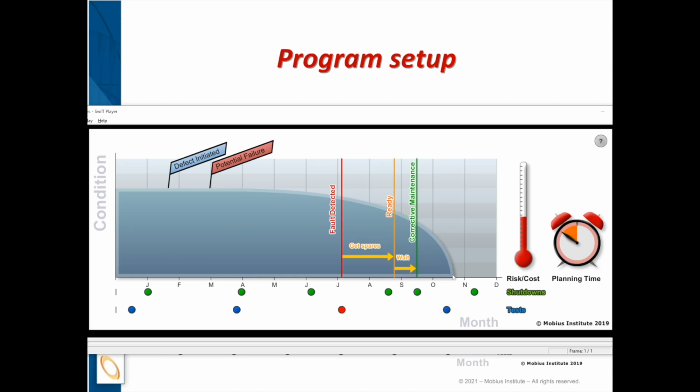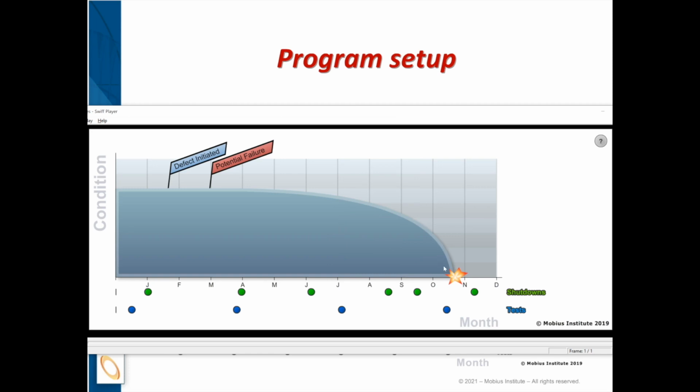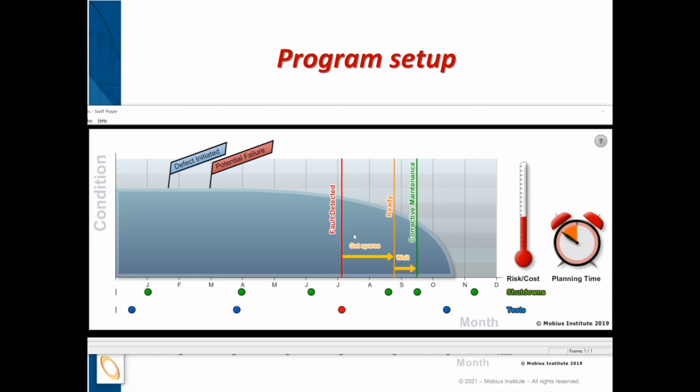You've just got to remember that you've got a certain interval between your tests and you've got a certain interval between the shutdowns. And you need to appreciate that, for example, if you perform a test here and you're thinking, I'll just keep watching the machine, and then your next test is here and you go, oh dear, look, the machine's almost failed.